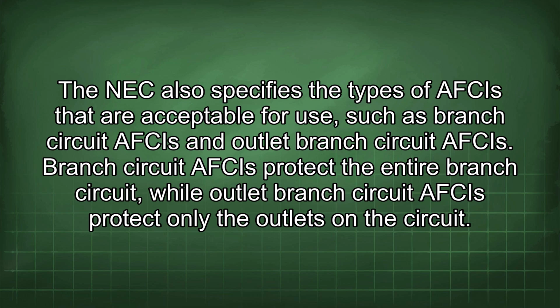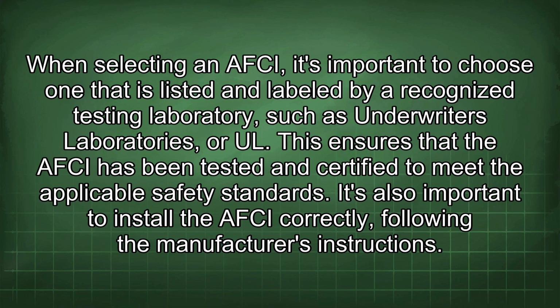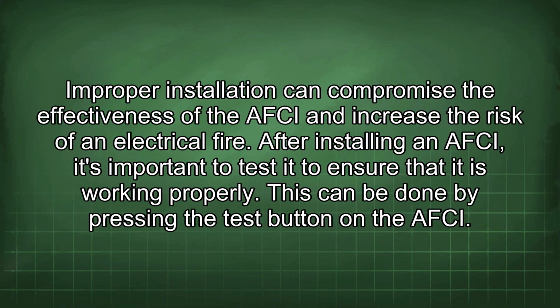The NEC also specifies the types of AFCIs that are acceptable for use, such as branch circuit AFCIs and outlet branch circuit AFCIs. Branch circuit AFCIs protect the entire branch circuit, while outlet branch circuit AFCIs protect only the outlets on the circuit. When selecting an AFCI, it's important to choose one that is listed and labeled by a recognized testing laboratory, such as Underwriters Laboratories or UL. This ensures that the AFCI has been tested and certified to meet the applicable safety standards. It's also important to install the AFCI correctly, following the manufacturer's instructions. Improper installation can compromise the effectiveness of the AFCI and increase the risk of an electrical fire.